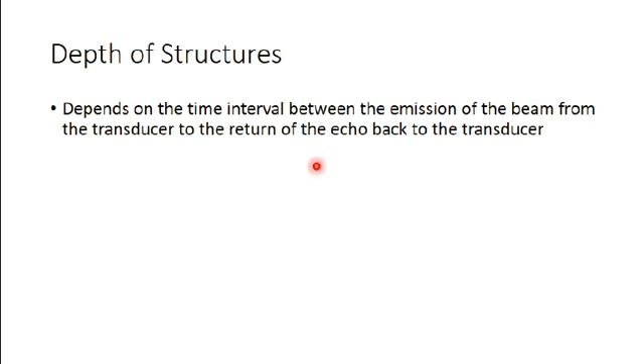Okay? Now, and how does this work? Let's go back. The principle of this is the speed or velocity of travel of ultrasound in soft tissue is relatively constant. It's about 1500 meters per second, which is 1.54 millimeters per microsecond. So what it means is that every microsecond the ultrasound beam will go in or come out 1.54 millimeters, 1.5 millimeters every microsecond.